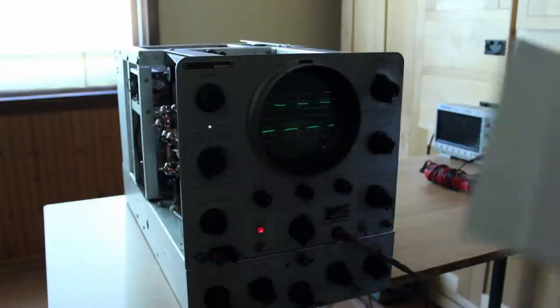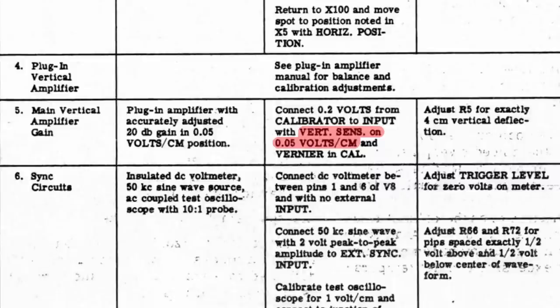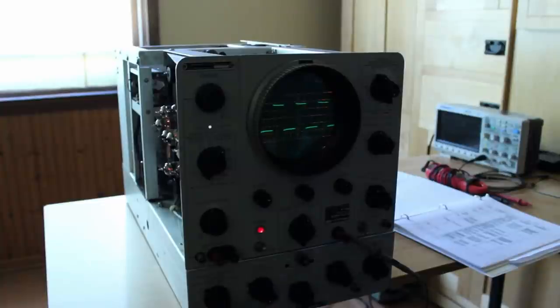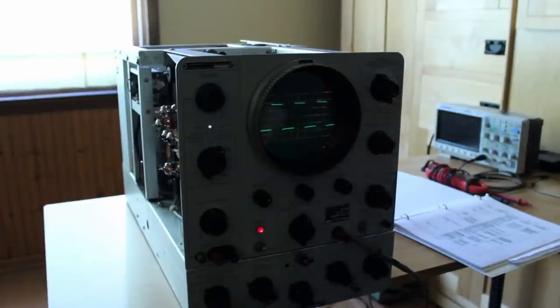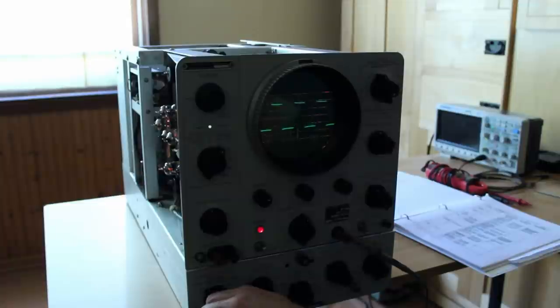I've got this set up like the manual outlines here for adjusting the vertical amplifier gain. This says to connect 0.2 volts from the calibrator to the input and set our vertical sensitivity to 0.05, then adjust R5 for exactly four centimeters of vertical deflection. I've got R5 maxed out and I'm not quite at four centimeters—I'm at about three and a half centimeters.